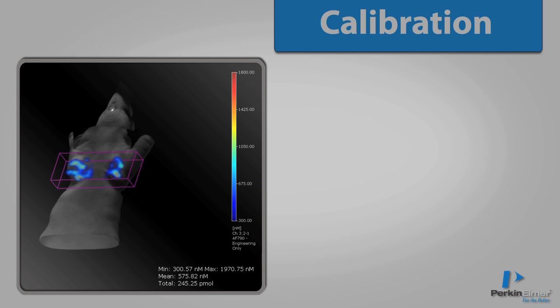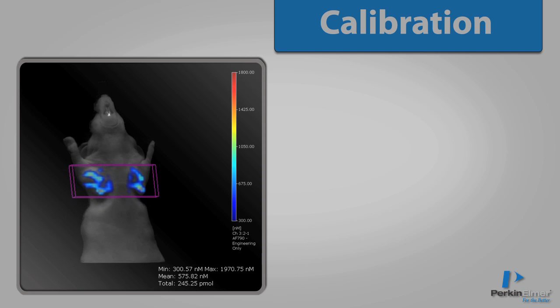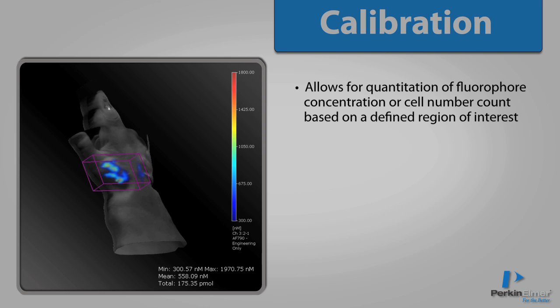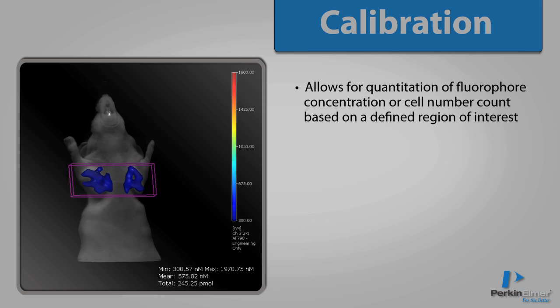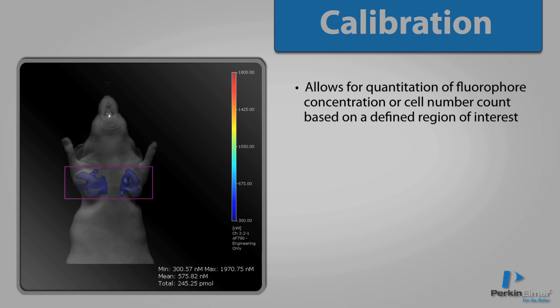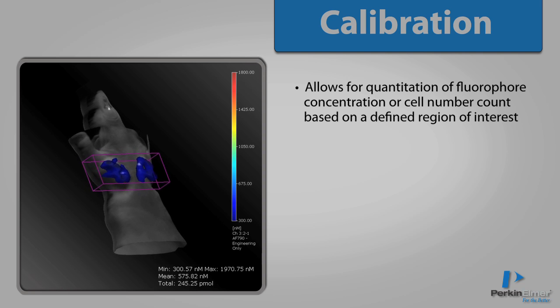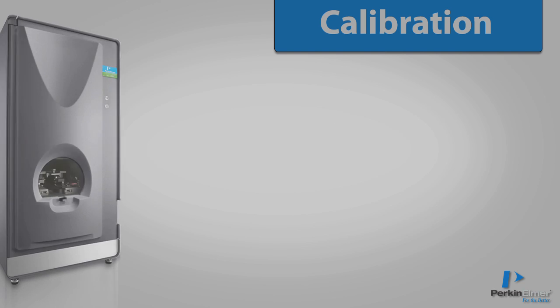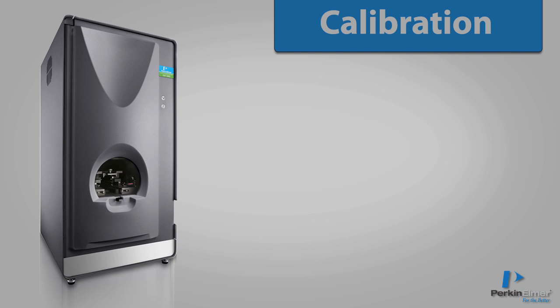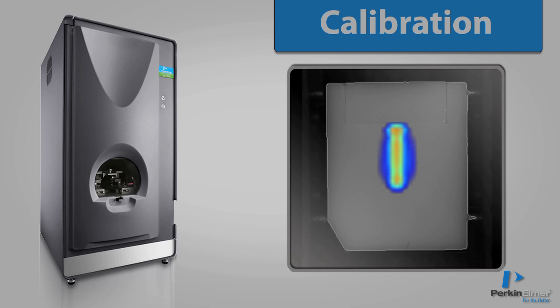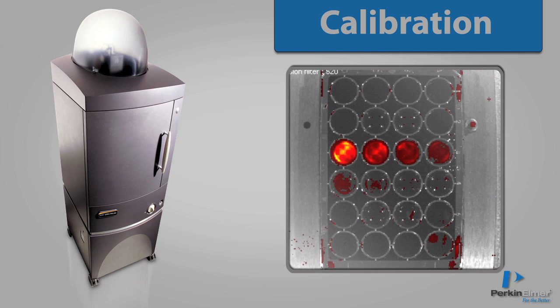In addition to data on the localization of a fluorescent source, 3D fluorescence tomography allows for the quantitation of fluorophore concentration or cell number count based on a defined region of interest. To do this, a calibration process must be employed to calculate a calibration factor relating the concentration of a fluorophore to its fluorescent signal intensity. In the FMT, this is done by measuring known concentrations of fluorophore using a rectangular phantom that approximates the light absorption and scattering process in tissue. In the IVIS system, a well-plate standard curve based on known cell number counts or concentrations of fluorophore is used.